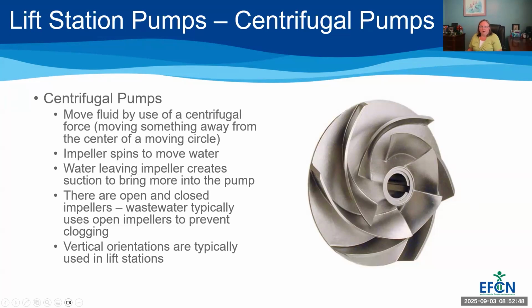And there are a couple of different types of impellers. There are opened and closed impellers. Closed impellers have a housing around this inner part, and we typically don't use those in wastewater because they can clog so easily. So typically open impellers are what we find in wastewater. And your centrifugal pump can sit horizontally or vertically. You see them horizontally in the treatment plants, but we see them vertically in our wastewater lift stations because that way the wet well doesn't have to be wide enough for the whole pump and motor to sit down this way. It can sit this way because they're going to be deep anyway. So typically oriented vertically in a lift station.